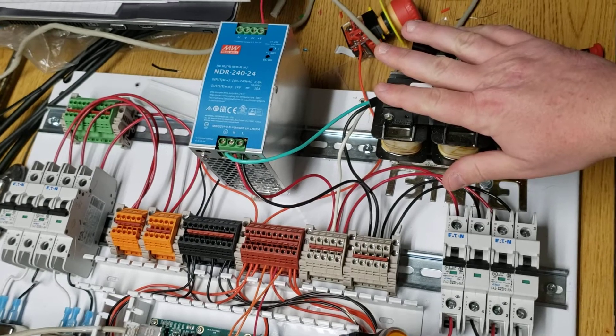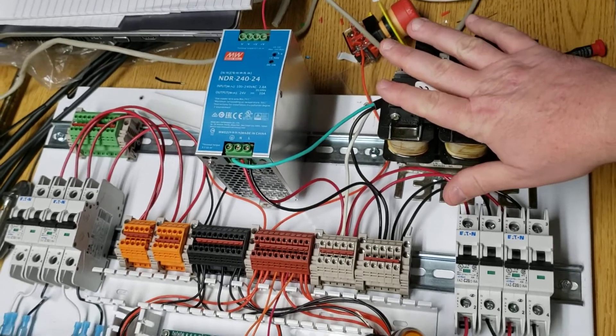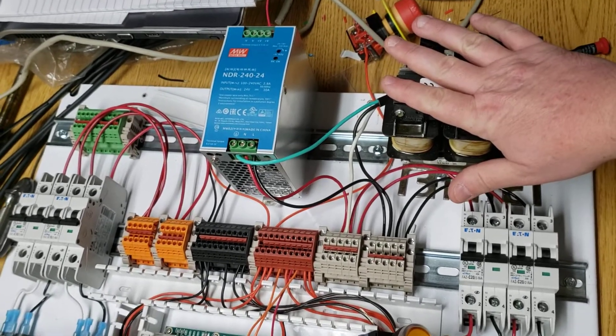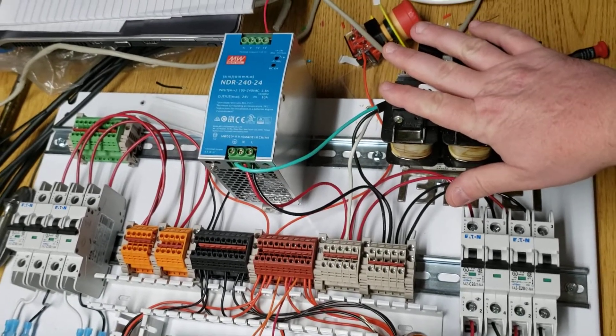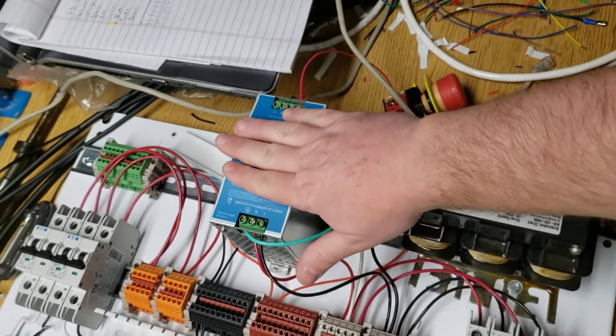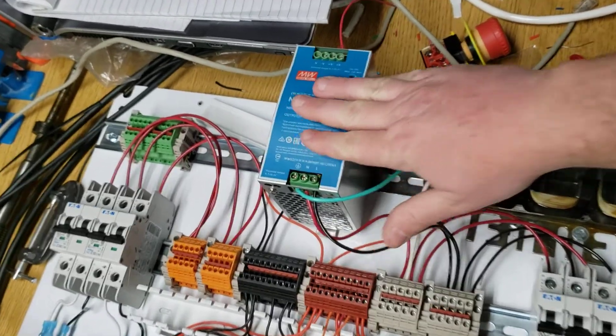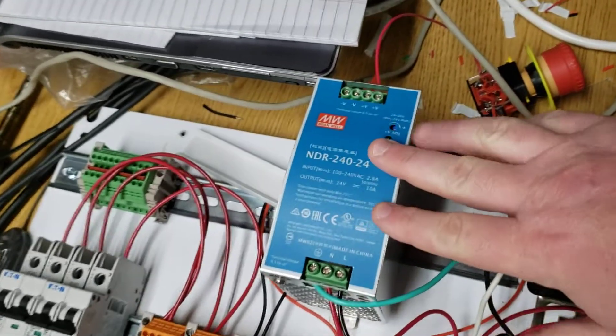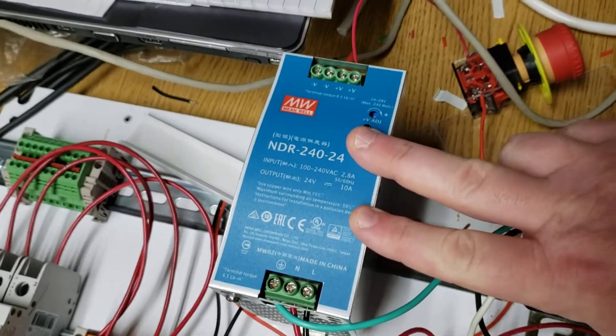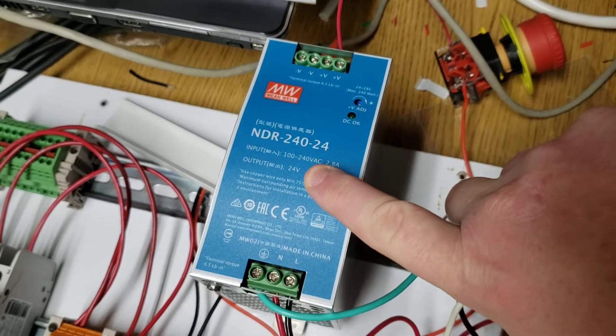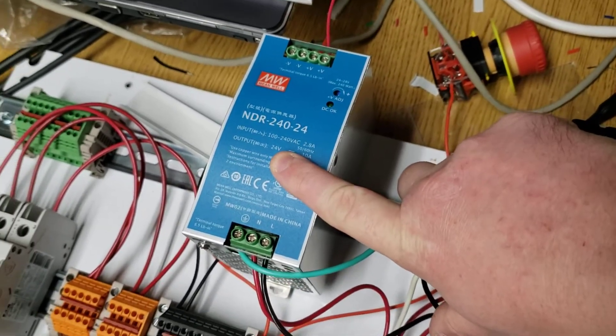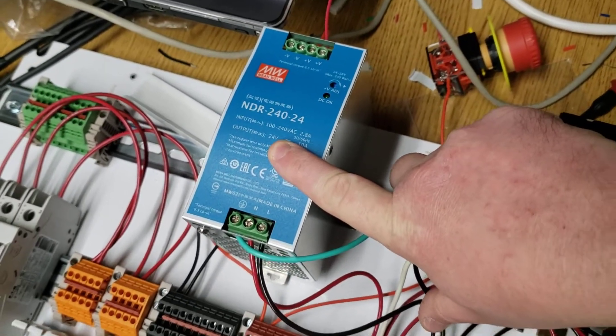From the line reactor, we're going to branch out to a couple of terminal blocks. We're going to power a 24 volt power supply—this is a universal voltage power supply, so I can run it off of 240. Output is 24 volt.